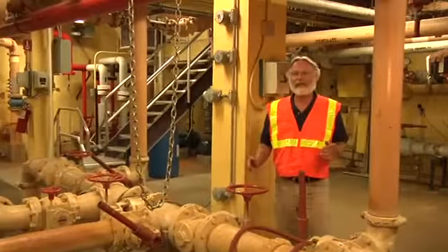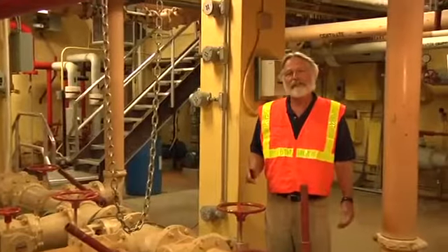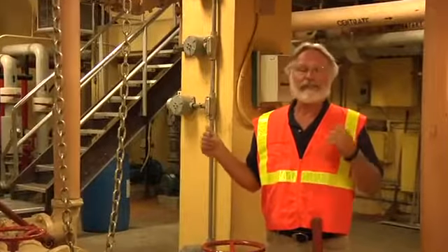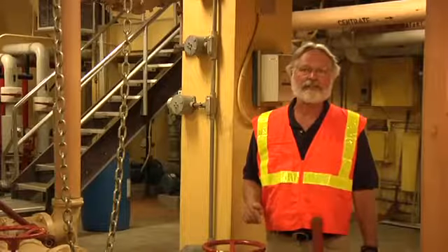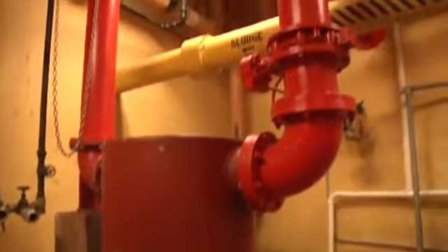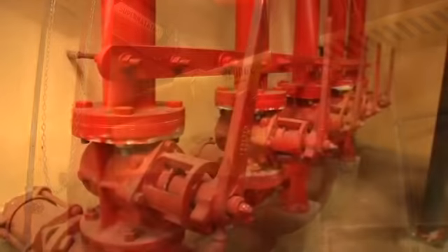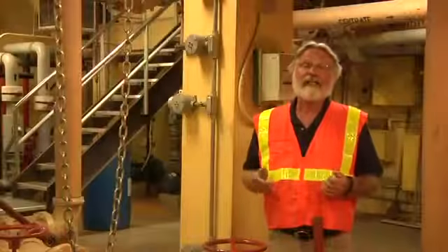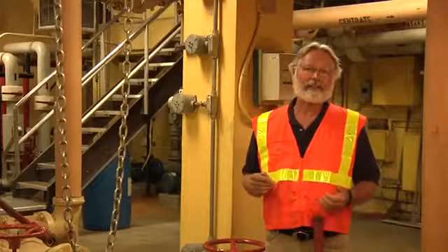We're in the pump gallery for the sludge digesters. We've thickened the sludge in the sludge thickeners and we've sent it over here to the digesters. In the digesters, we heat the sludge up and the microorganisms start to break it down, get rid of some of the volatile compounds, make it to where it won't degrade any further. In that process, it also destroys some of the pathogens.